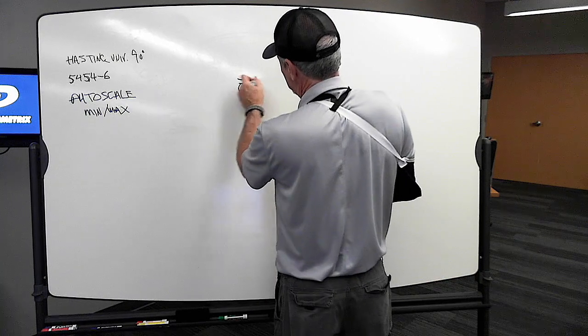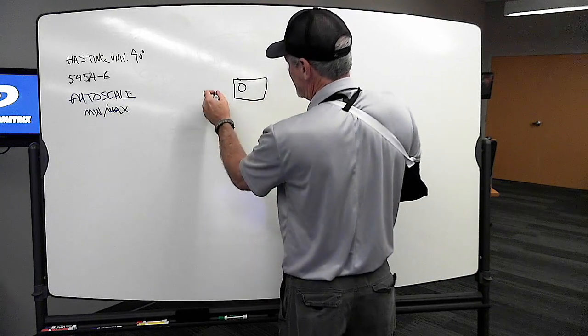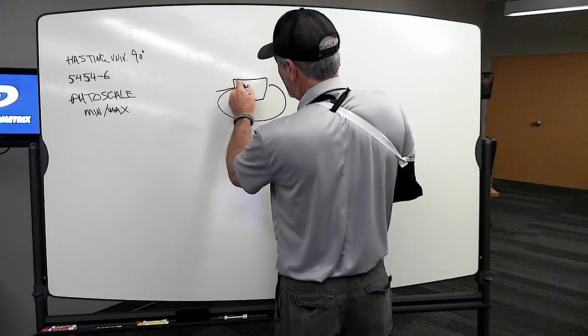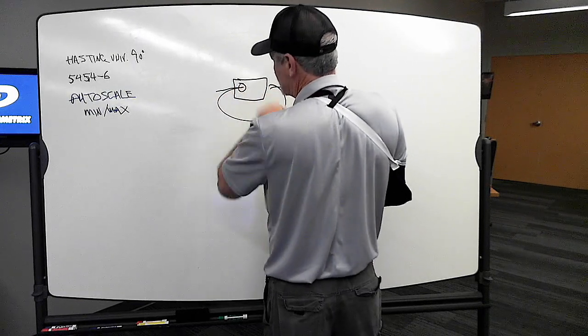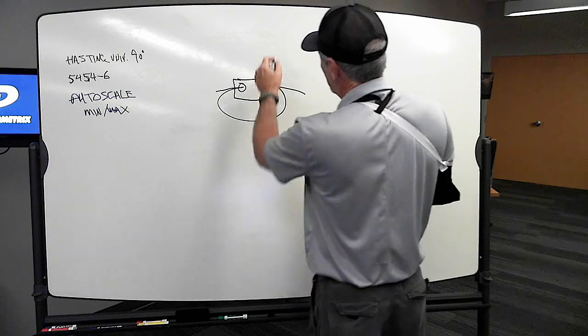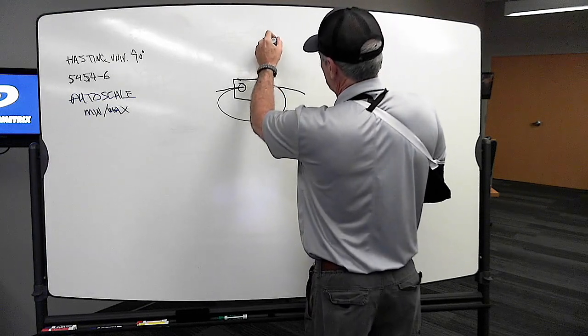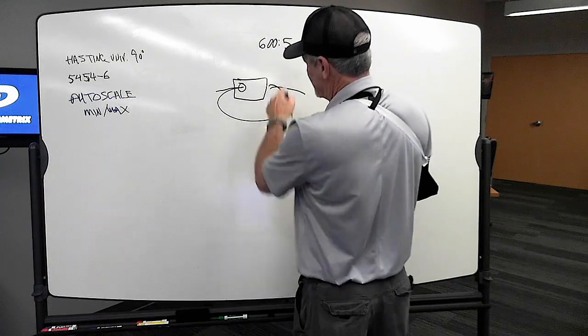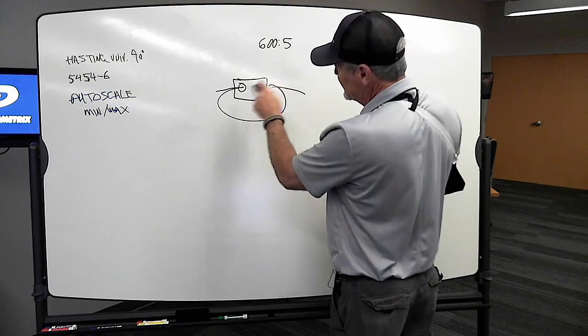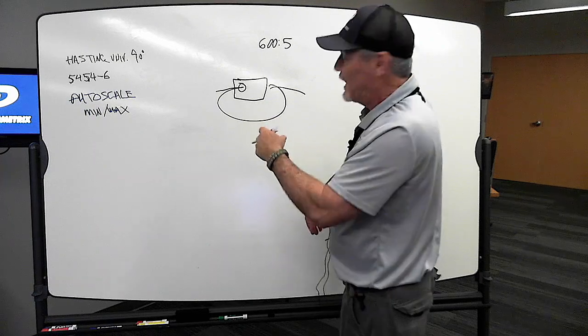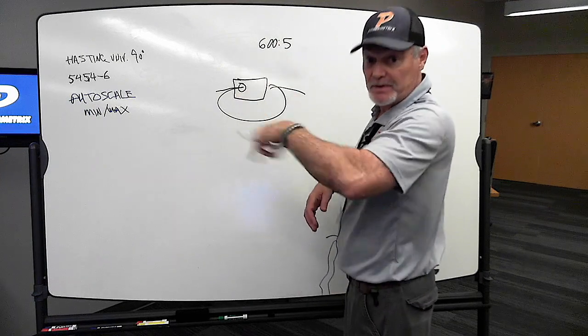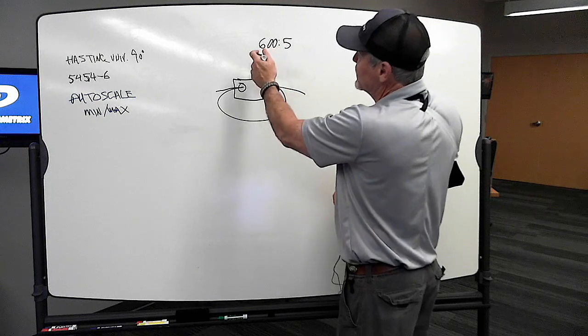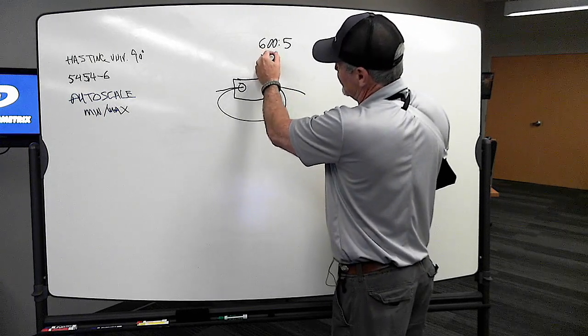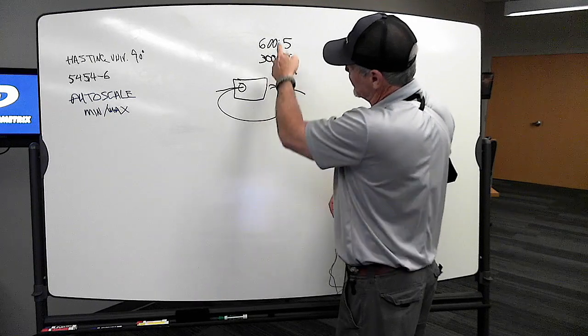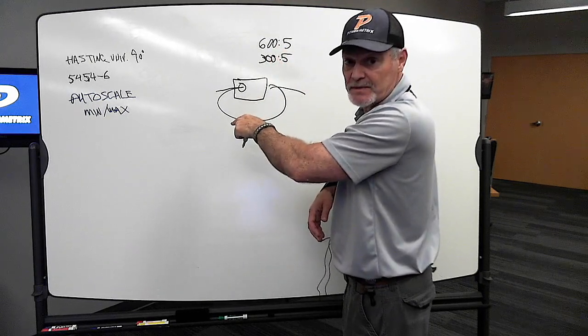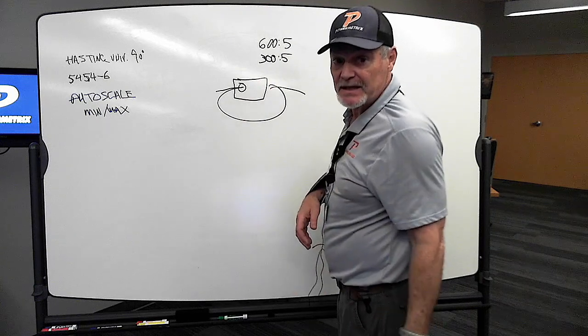If I have my CT and I run an extra loop through there, what happens if I run it through twice? If this is a 600 to 5 CT, and I double loop through it, I can't run 600 through there anymore, because I'm pumping twice as much through there, twice whatever that number is. So now I've derated it, really now it's a 300 to 5. Because if I ran 600 amps through that conductor, it's really 1200 going through that CT.